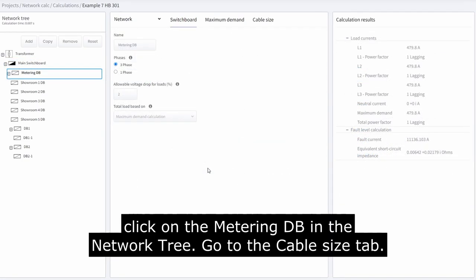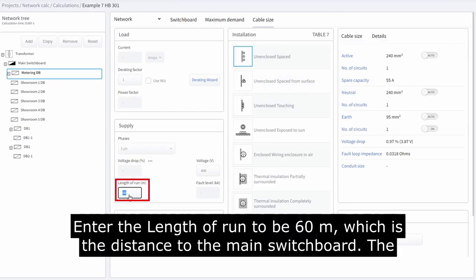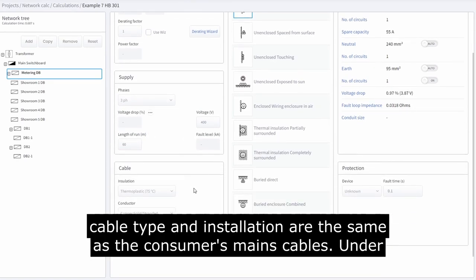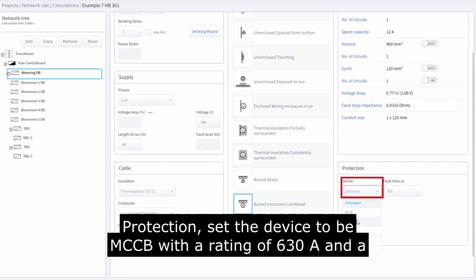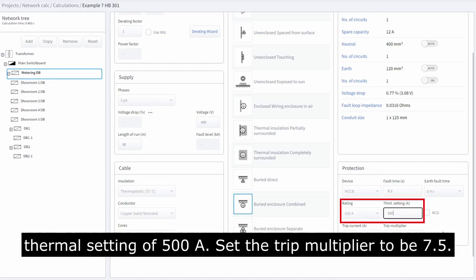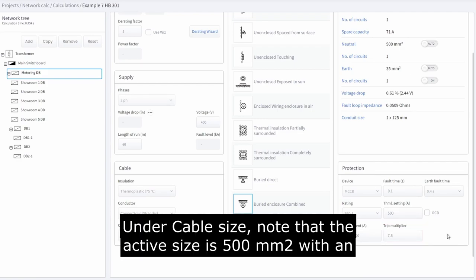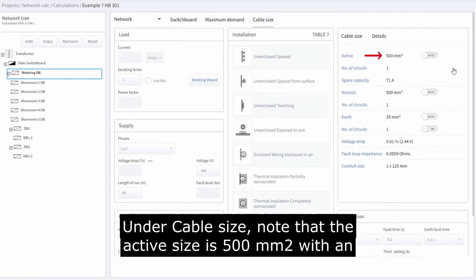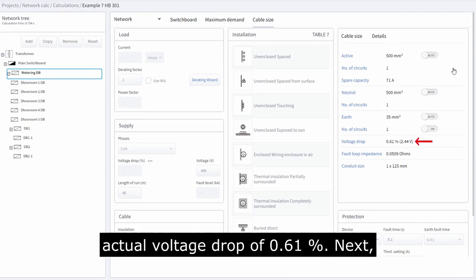Next, click on the metering DB in the network tree and go to the cable size tab. Enter the length of run as 60 meters, which is the distance to the main switchboard. The cable type and installation are the same as the consumer's mains cables. Under protection, set the device to be MCCB with a rating of 630 amps and a thermal setting of 500 amps. Set the trip multiplier to 7.5. Under cable size, note that the active size is 500 mm² with an actual voltage drop of 0.61%.